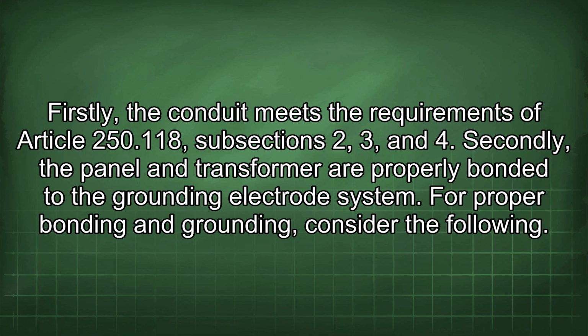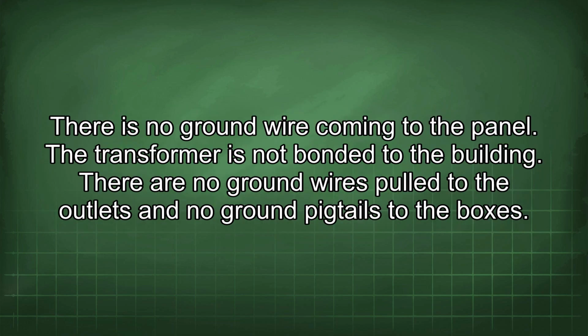For proper bonding and grounding, consider the following. There is no ground wire coming to the panel. The transformer is not bonded to the building. There are no ground wires pulled to the outlets and no ground pigtails to the boxes.